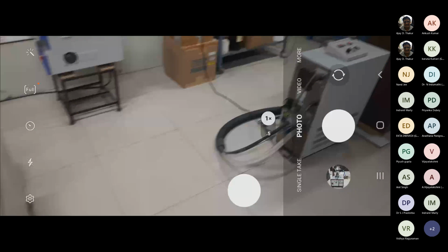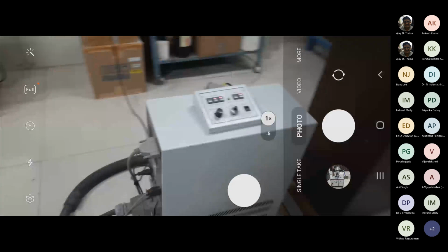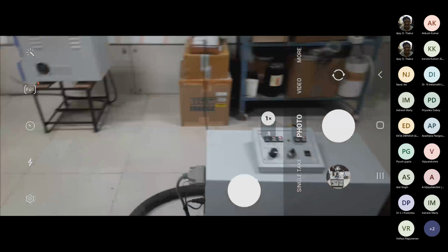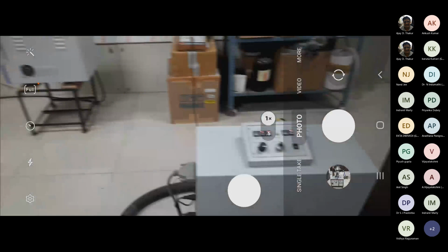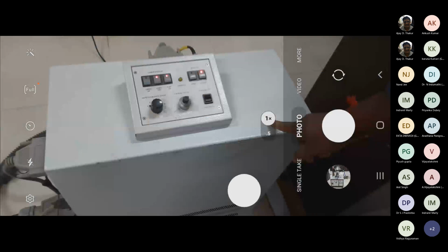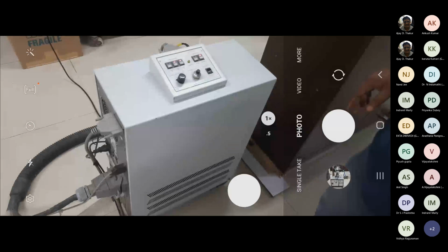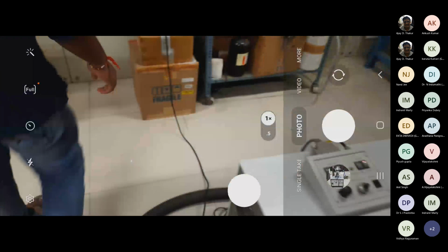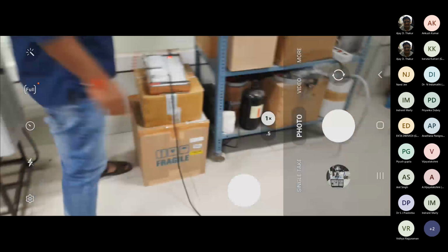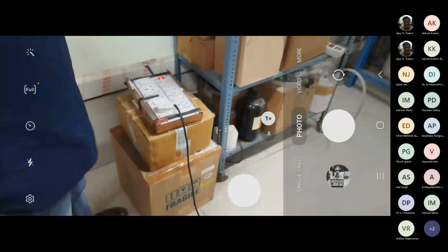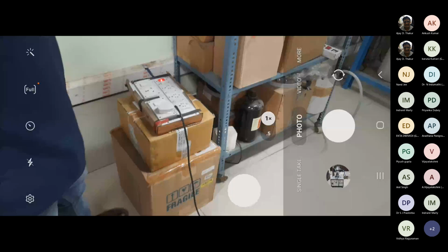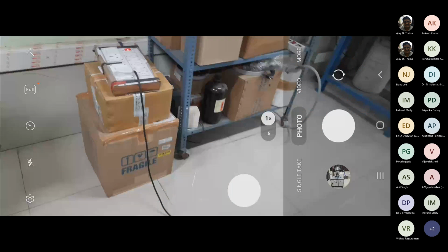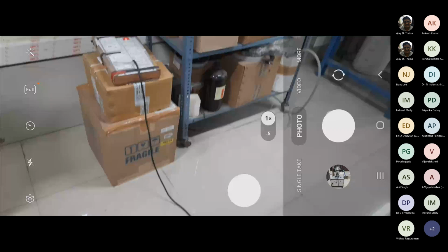Yeah. So this is the laser part, where this is the chiller of the laser, because the laser power supply, the optical pumping and the chiller are all in a compact unit. And the power supply is also connected to a constant power supply source, which is kept behind the system. It is a 3 kVA constant power supply unit, through which the line was connected.